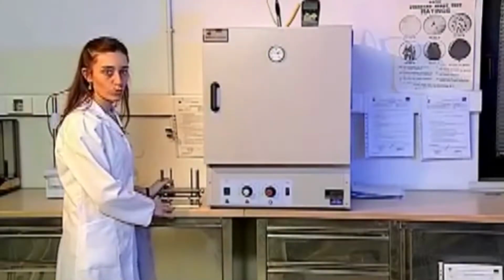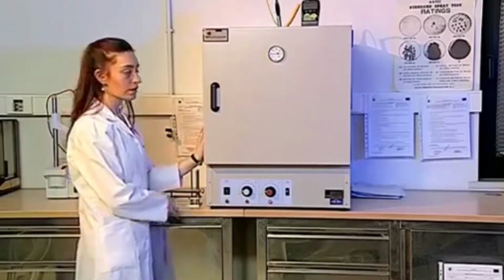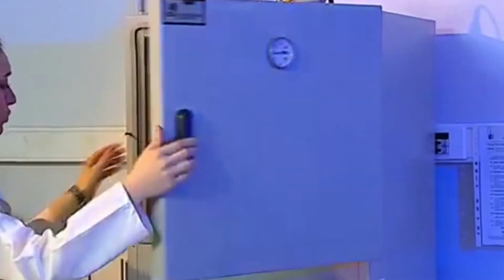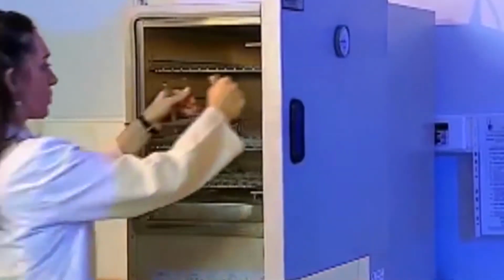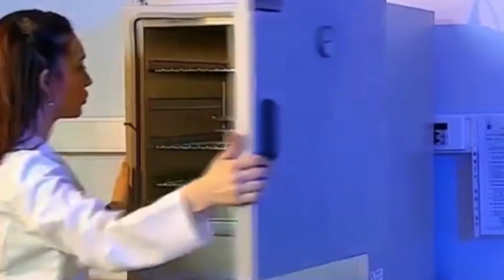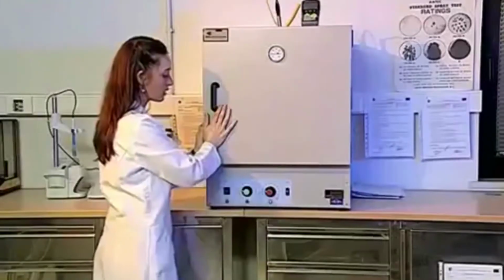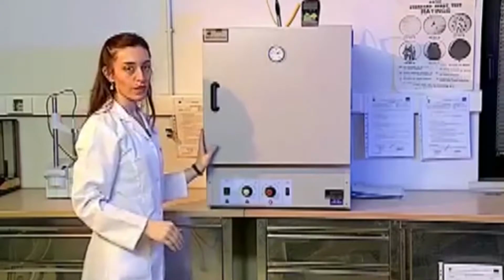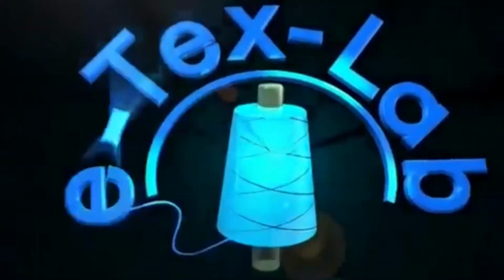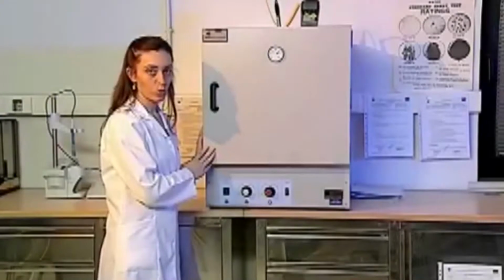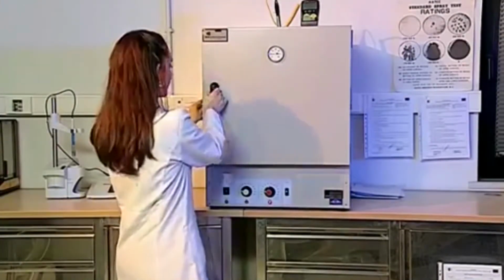The sample is placed vertically into the oven previously adjusted to 37 degrees centigrade. The oven must be closed quickly to prevent the temperature from falling. And then we wait for 4 hours. The sample is removed from the oven after 4 hours.